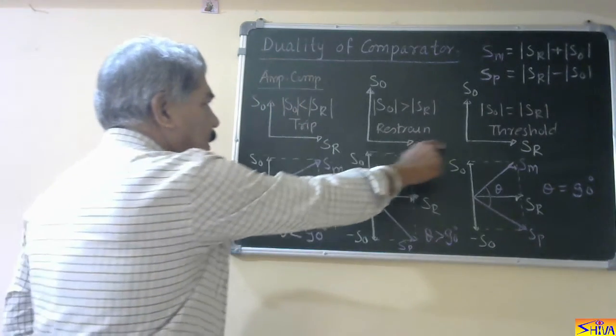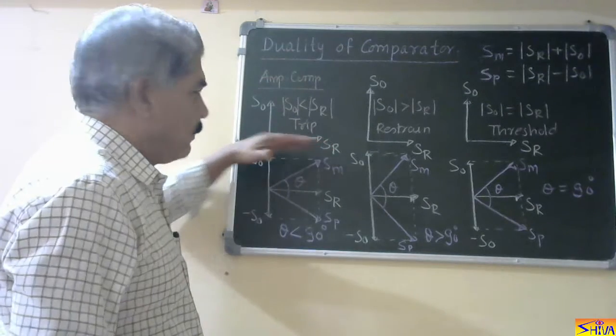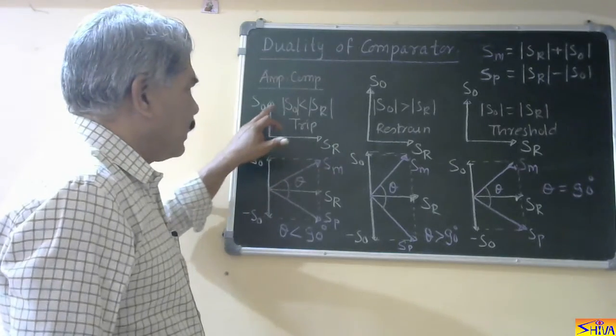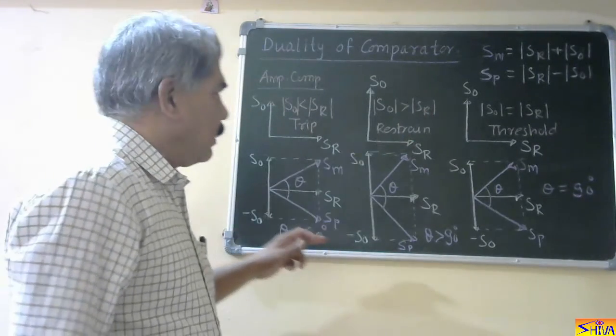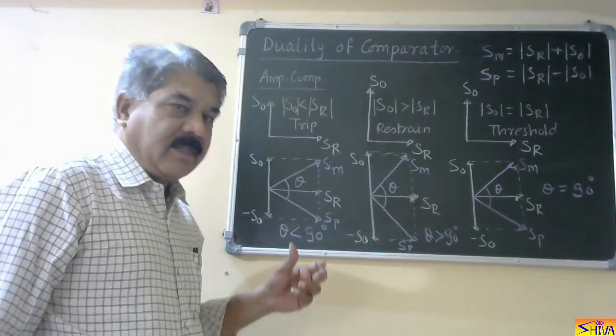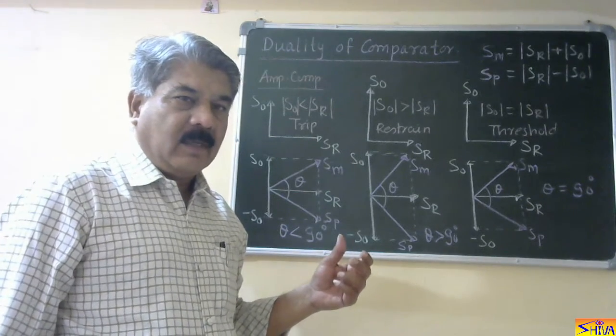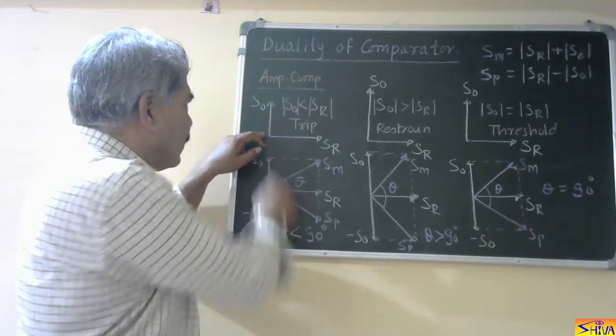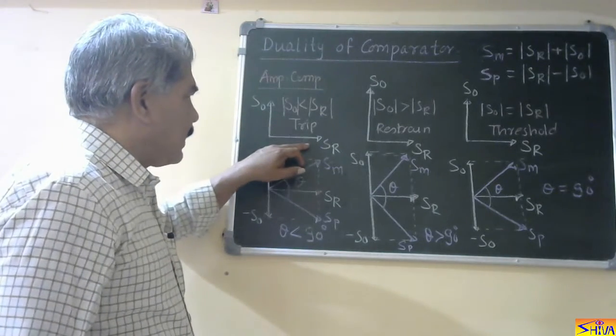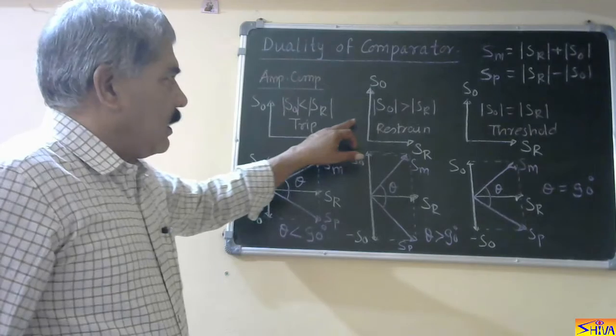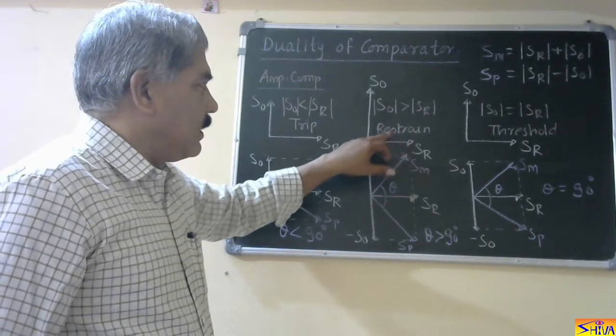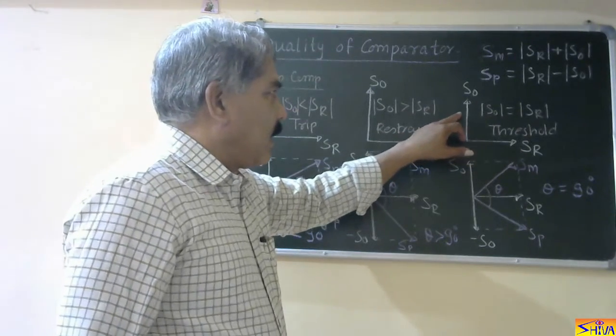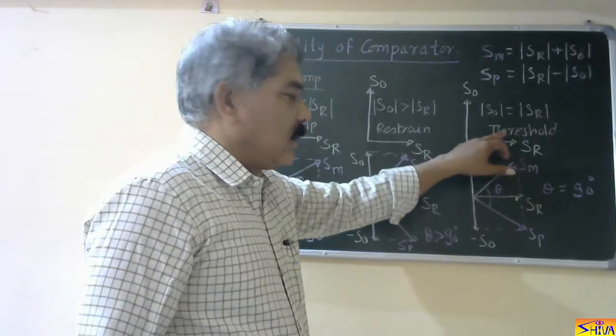The amplitude comparator conditions are shown. SR is the reference quantity and SO is the operating quantity. When SO is less than SR, this is the trip condition. When SO is greater than SR, this is the restraining condition. When SO and SR are both equal, this is the threshold condition. For simplicity, the angle between the two quantities is fixed at 90 degrees.